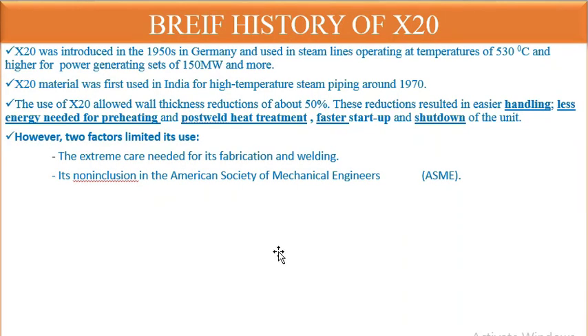A brief history of X20: it was introduced in the 1950s in Germany and used in steam lines operating at temperatures of 530°C and higher for power generating sets of 150 MW and more. X20 was first used in India for high-temperature steam piping around 1970. Its use allowed a wall thickness reduction of about 50%, resulting in easier handling, less energy needed for preheating and post-weld heat treatment, and faster startup and shutdown.